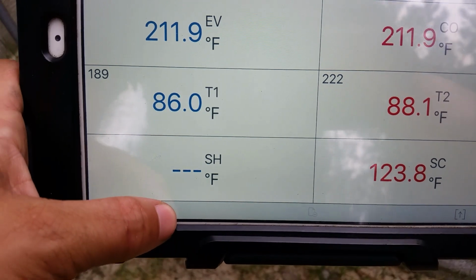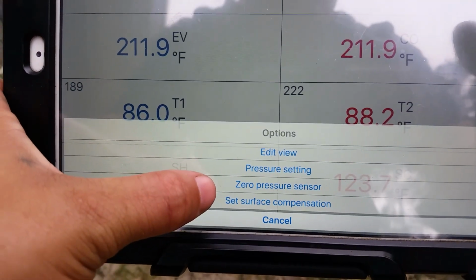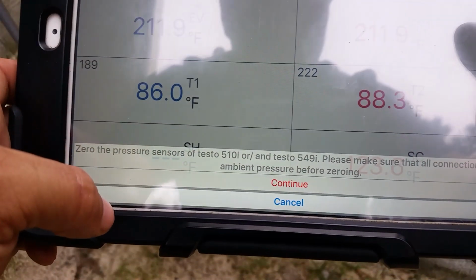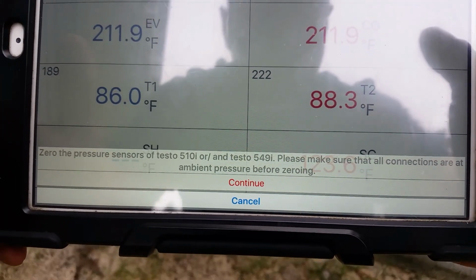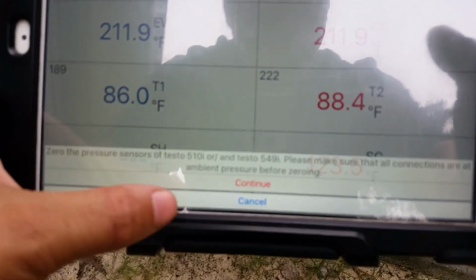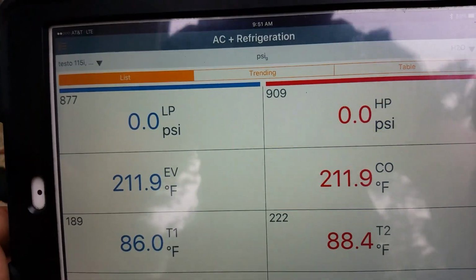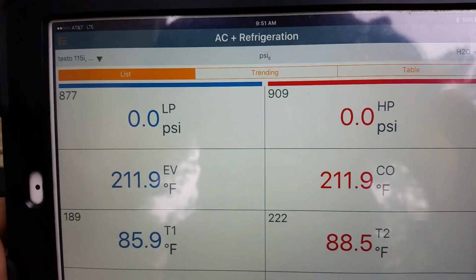If you do have to zero them, it's very easy. All you do is hit the little gear down here, go to zero pressure sensors. It's going to tell you to make sure they're not connected to anything, and that they're open to ambient pressure. Hit OK, and it will zero the gauges.